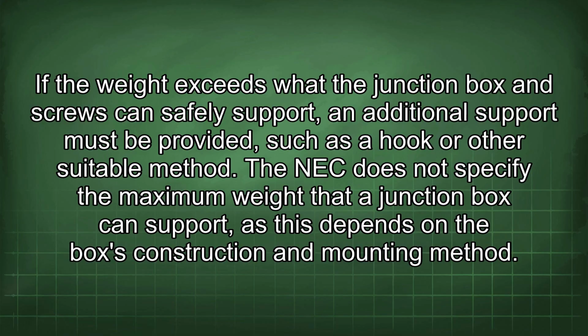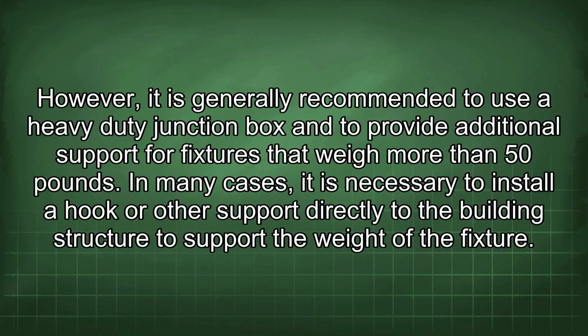The NEC does not specify the maximum weight that a junction box can support, as this depends on the box's construction and mounting method. However, it is generally recommended to use a heavy-duty junction box and to provide additional support for fixtures that weigh more than 50 pounds. In many cases, it is necessary to install a hook or other support directly to the building structure to support the weight of the fixture.